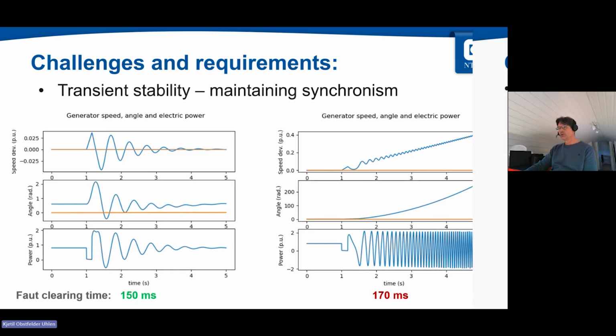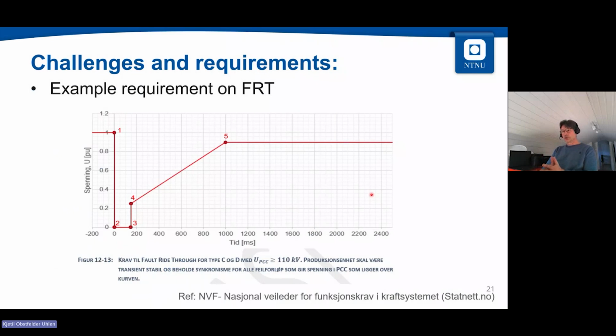So that is also one of the motivations for having requirements on fault ride-through. This is from the Norwegian requirements by Statnett. And you see here that we require that you can ride through faults that on the high voltage side go through zero and maintain for 150 milliseconds. So in this case, my generator would fulfill the requirements, but this is quite tough. And the reason why it goes to zero is, of course, that with less short circuit current contributions, you will also see more risk of voltages going down to zero during a short circuit.